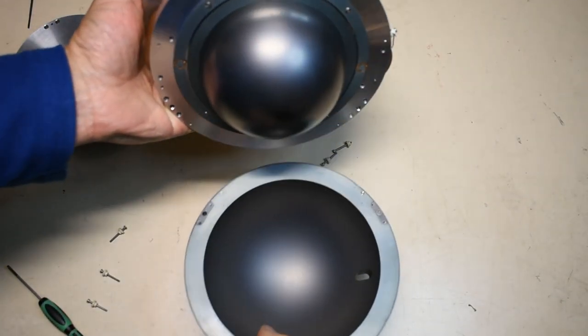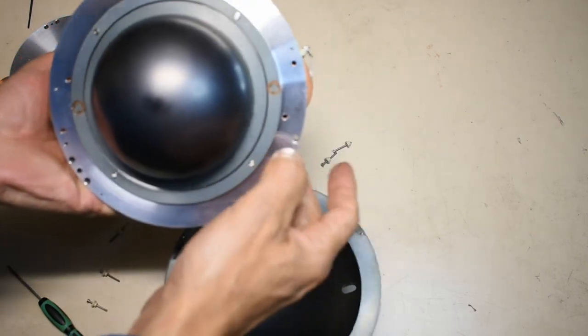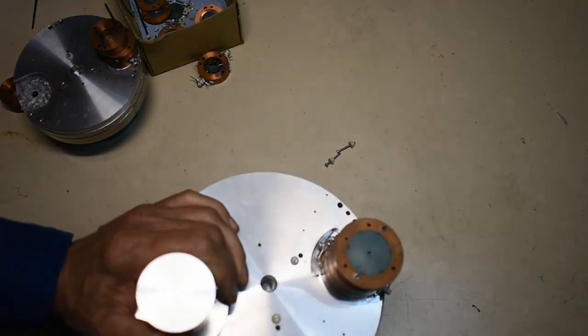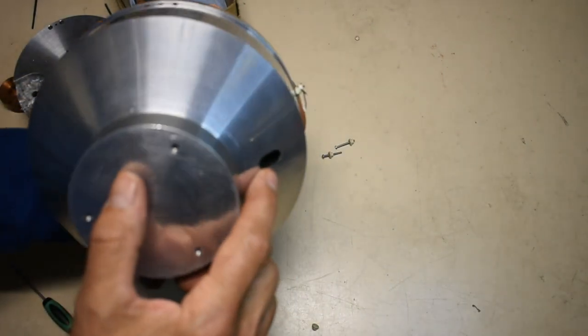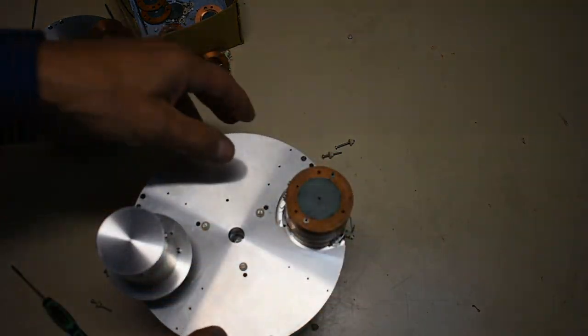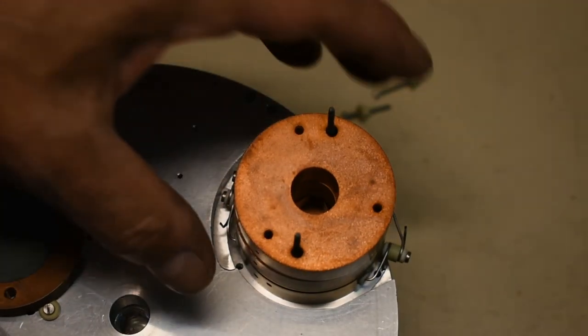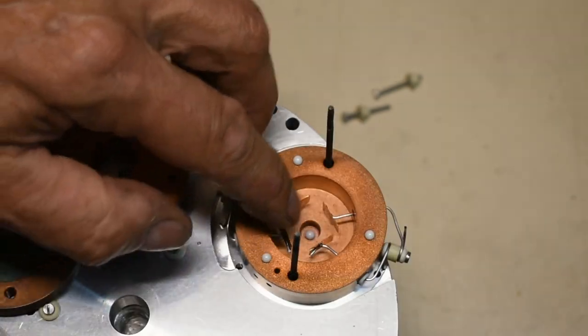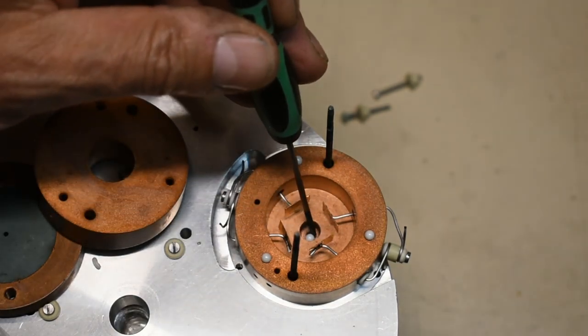Well the interesting thing on this one is there's actually a hole here that lines up with where the beam would come through here. See there's actually a hole which lines up with the electrostatic lenses here. When I take it apart there are some electrostatic lenses and again deflection ones here and one of the little glass beads has actually fallen inside.